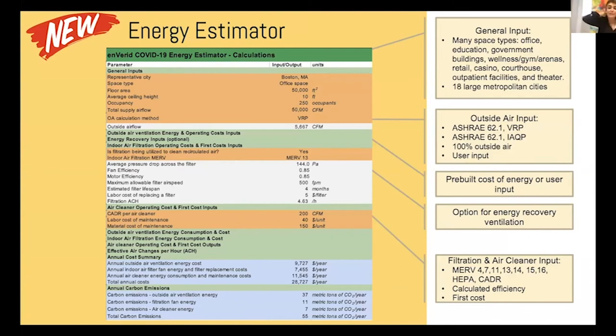But basically, what's nice about it is you can use the other tools to calculate the air exchange rate or to calculate the risk. It's optional. Or you can use this energy estimator. This is a standalone energy estimator to tell you the first cost and operating cost for ventilation with outside air for different filters. It has pre-built efficiency, so you can choose any filter you need. It has pre-built in it the pressure drop. How much is it going to cost? And also any type of air cleaner you want is here. I hid a lot of these rows because I needed to fit them on one slide. Also, you can choose what strategy, what type of building, etc.